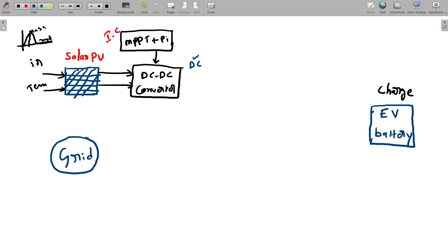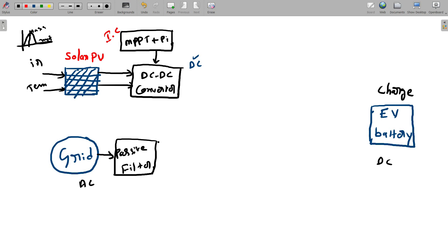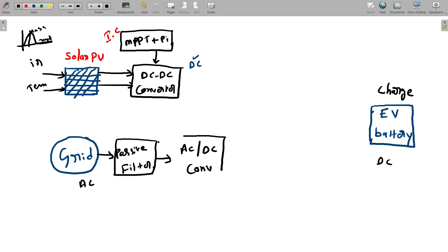Coming to the grid side, the main problem is that the grid supplies AC, but the EV electric vehicle requires DC. So first, we need to convert AC to DC with an AC-to-DC converter — essentially a rectifier. Before that, we need to connect one passive filter to reduce any harmonics coming from the grid. After the passive filter, I connect the AC-to-DC converter. This converter is bidirectional — we are taking a bidirectional AC-to-DC converter.